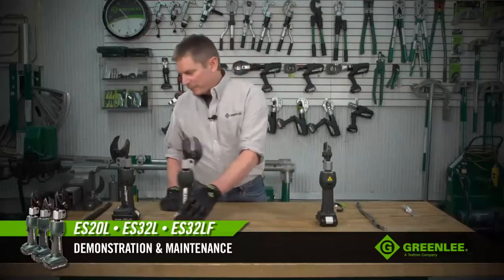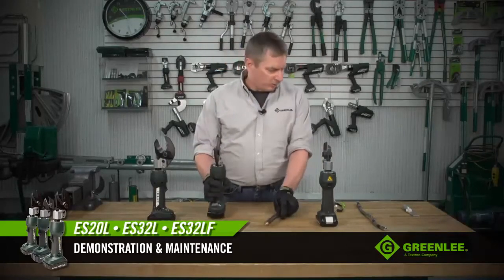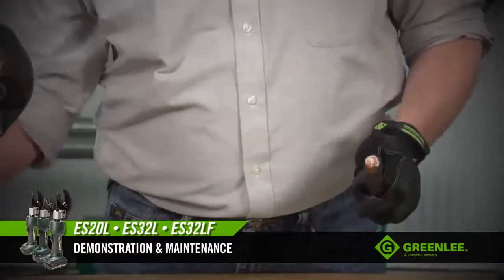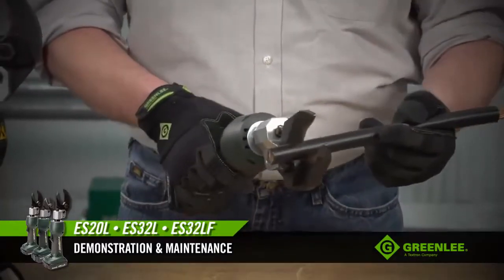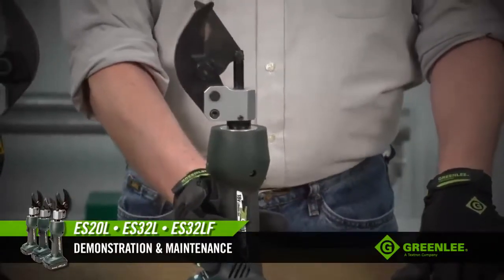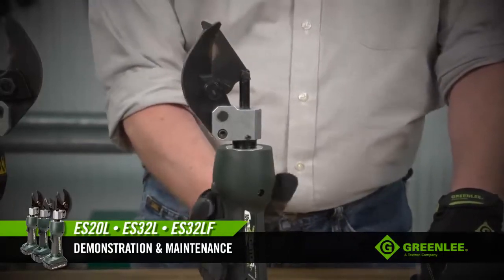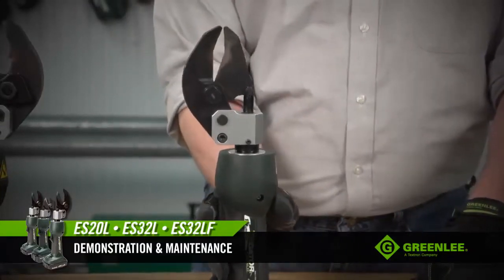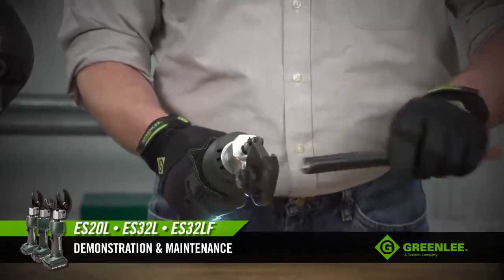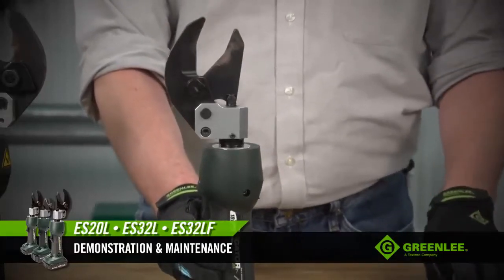Let's do some demonstrations. This is a piece of 3/0 copper. Before doing any type of cutting, always remember to put your safety glasses on. The operation is simple — just place the cable between the blades. You'll notice that the blades did not open after cutting through the material. There are two ways to continue: you can either hit the manual retract right after the cut, or continue holding the trigger so the tool cycles completely and the blades will open automatically.